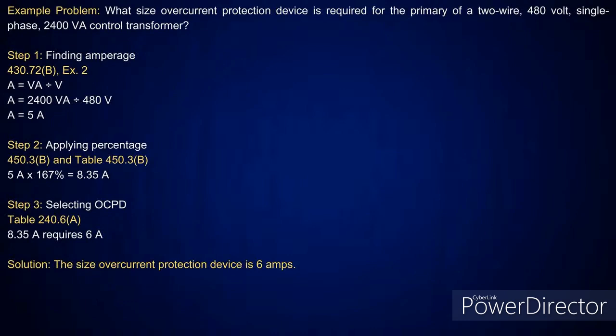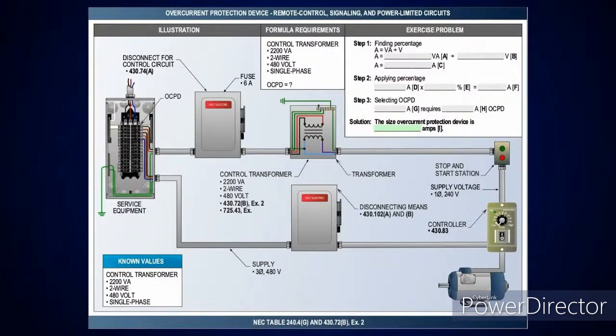But when you look at that table, you're going to notice there's no superscript 1 there, like we talked about the other day. So if there's no superscript, what do I do? I drop down again. Yep. So you take the 5 amps at 167%, that's going to give me 8.35 amps. So the next size below that, standard size per table 240.6A, is a 6 amp overcurrent protection device.